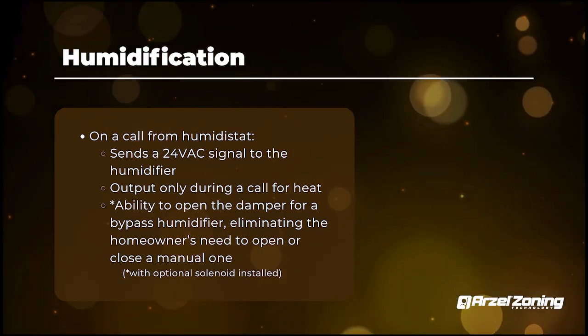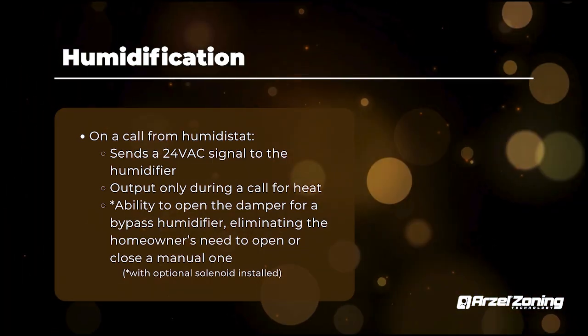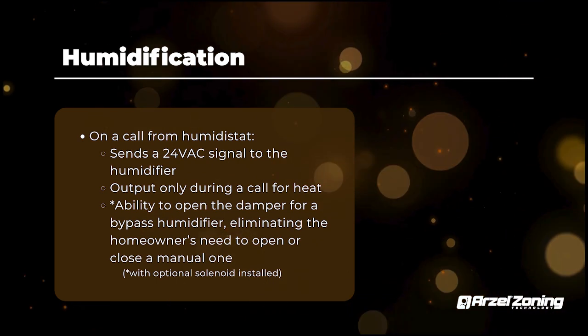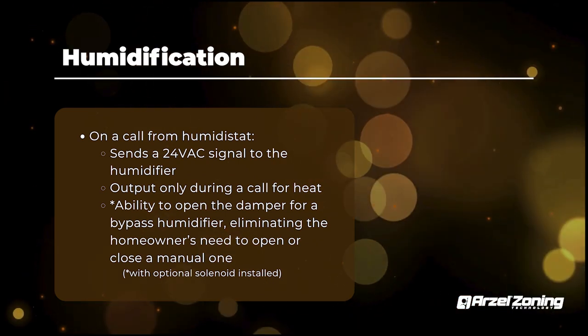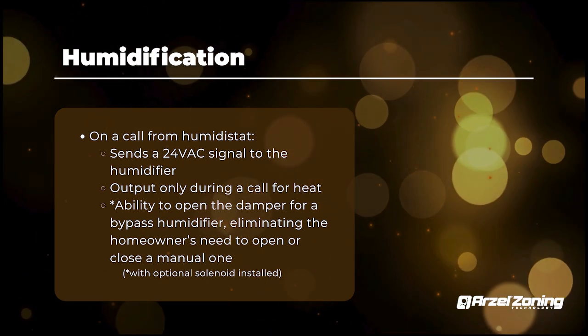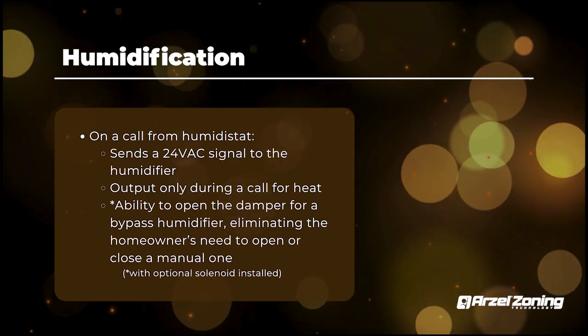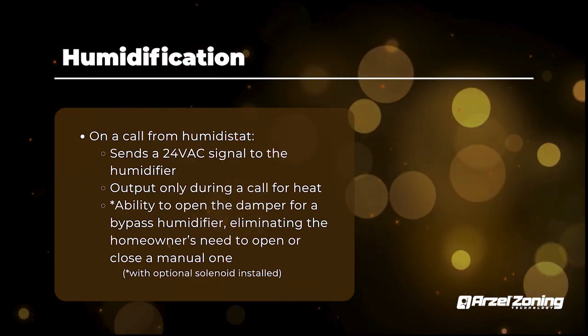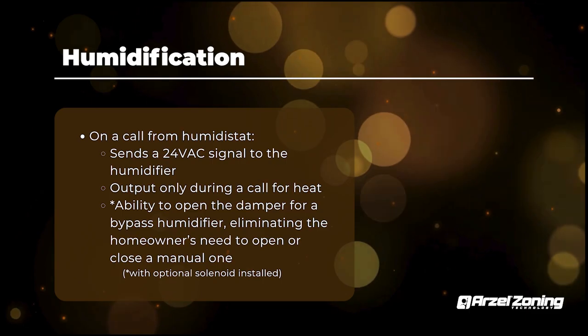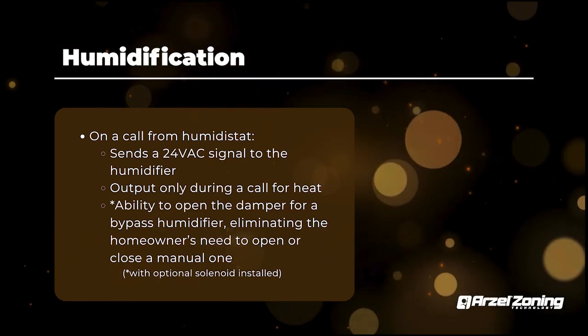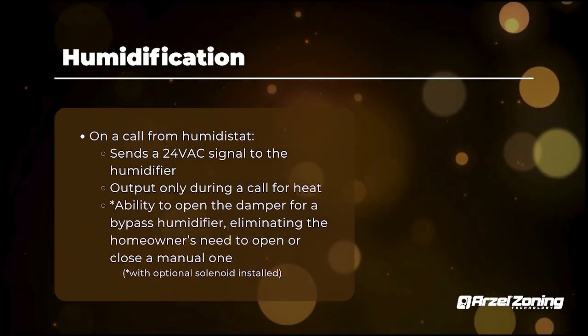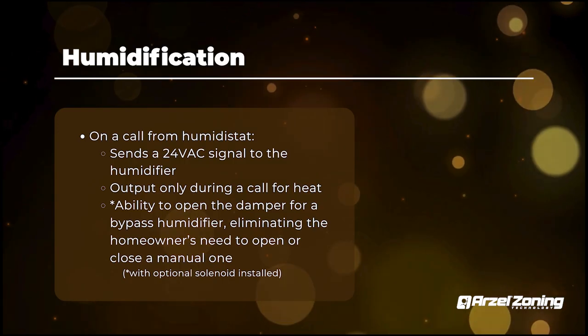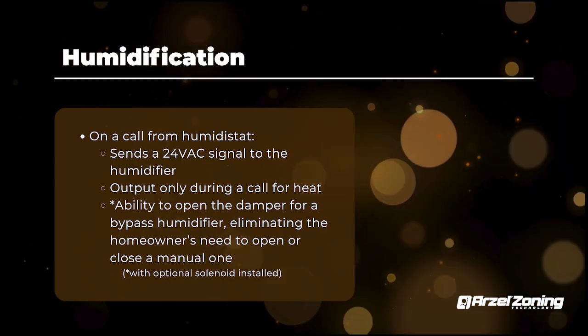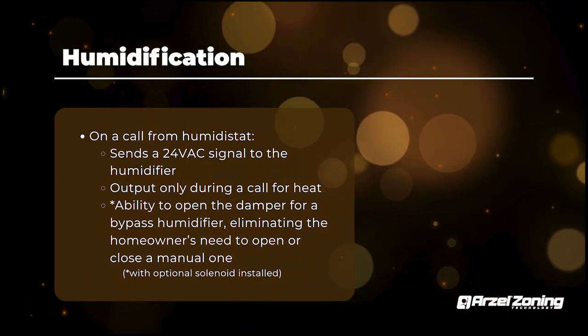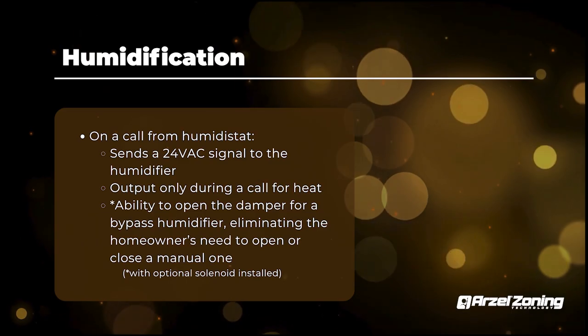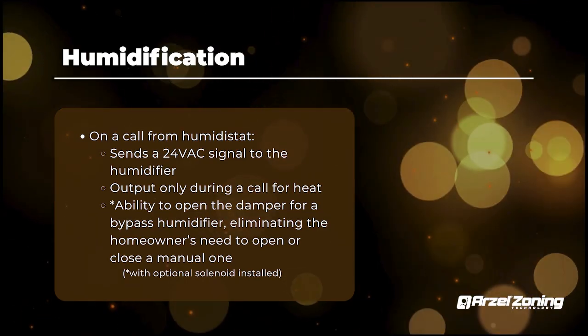And one of the nice functions as well, if you guys do end up using that humidifier terminal on the HeatPumPro and they're using a bypass style humidifier, you can actually order that panel custom with its solenoid built in for the bypass on the humidifier. So instead of your customer having to open and close that bypass on the humidifier itself, it would actually open anytime there's a call for humidity. So they would never have to go downstairs every season and open and close that bypass anymore. It would do it automatically for them. So that is an option as well.